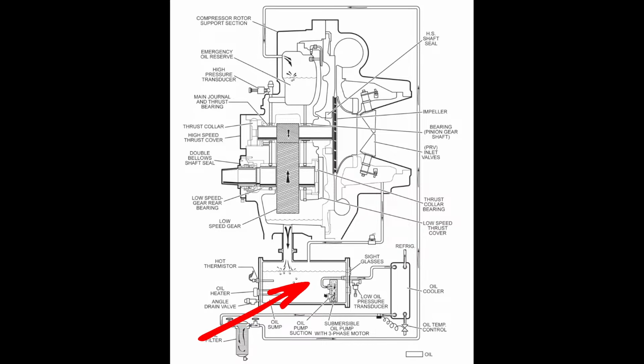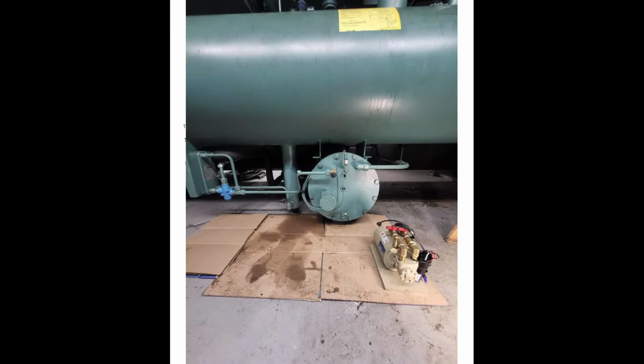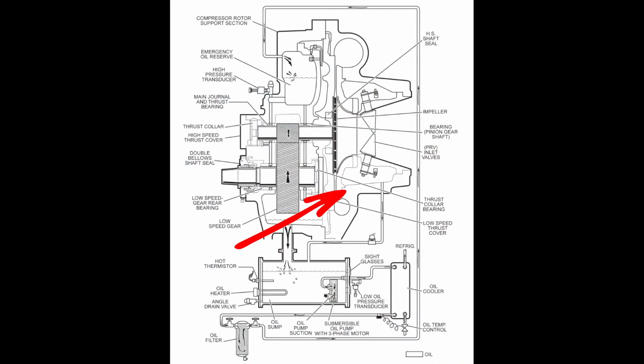That should be enough. And I'm assuming yours is the style where you've got the full front face glass. You don't have just the two glasses like what I showed here, right? So with this one, we literally just have the two glasses there, right here. Whereas some of the designs, we can see the full column in between those glasses. So either way, 85%, that should be enough oil, so we can eliminate that, right? We haven't eliminated the sensor necessarily, but we have eliminated the oil heater and the level, so we know those are functioning.